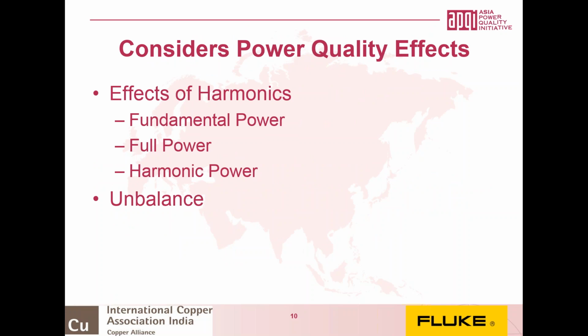So in the simplest terms, for the physical components that we pull out, we consider first of all the effects of harmonics, and we break this down into the fundamental power, the full power, and the harmonic power. And these are terms which are described in 1459, but are not necessarily pulled out in exactly this way. And then the other area, of course, is the unbalance. So breaking down into these separate components allows us to consider mitigation for each of the effects separately.